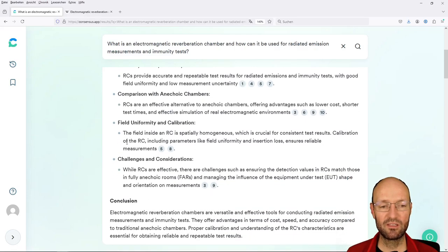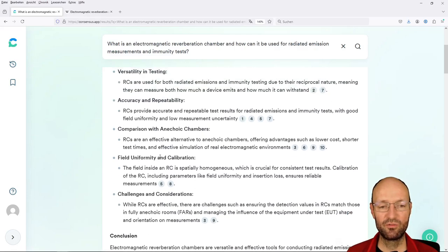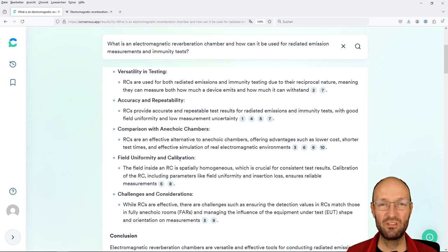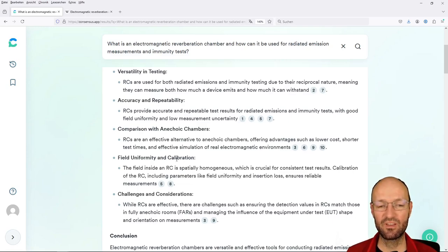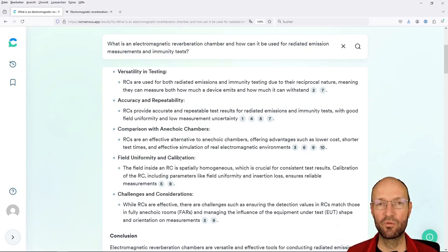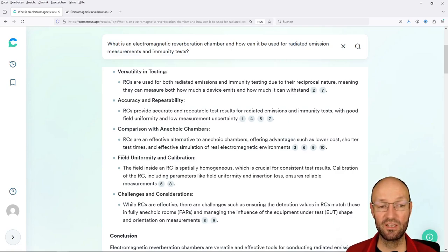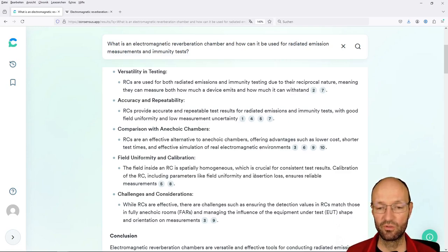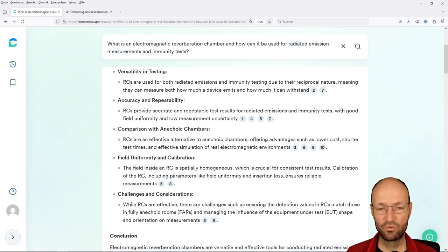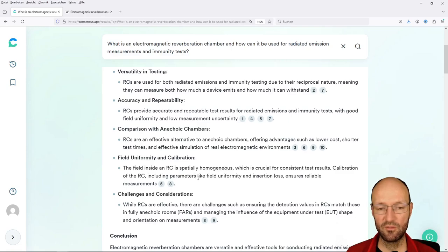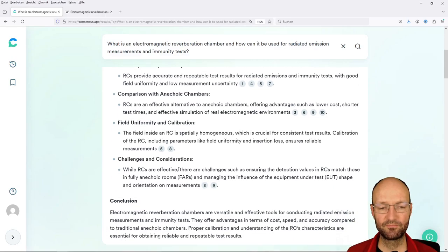One important aspect is field uniformity and usually nowadays we would say rather validation instead of calibration. Once again, it's a thing how you define this, but there are for sure many old papers older than 10 years, 15 years that would rather speak of calibration instead of validation to check is there sufficient field uniformity, is the isotropy of the field good and so on.